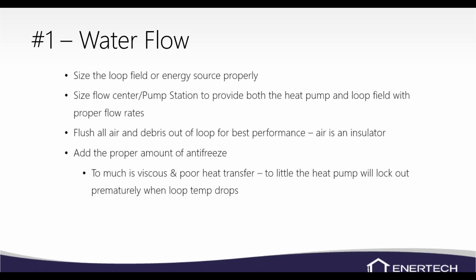Make sure we've got antifreeze in the system. The majority of the time, we design the systems for about 30 degrees as our lowest temperature on a perfect day, or a design day. We get times when we're below our design temperatures, so we know we're going to drop that loop field temperature below freezing at times. And so we've got to make sure that we've got the proper amount of antifreeze in there so it doesn't freeze up. But I would highly recommend don't just dump straight antifreeze in there, because then the antifreeze becomes too thick, or too viscous, and it doesn't transfer heat as well. Lock out prematurely, and it can also cause problems with your pump as well.